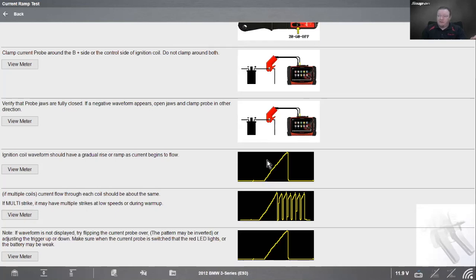If it goes up sharply and then over, I have a bad coil. I have bad windings in that coil. It's too much resistance it's trying to overcome to add that voltage into the coil. So we would have a high spike in the ramp, and then it might go over.